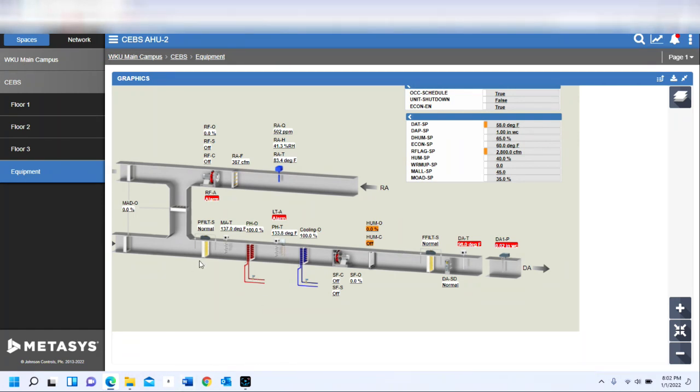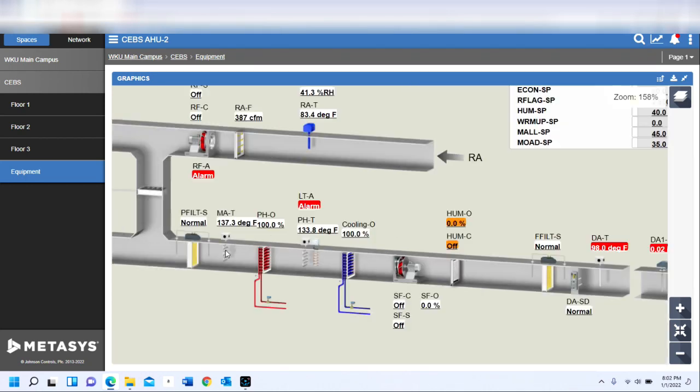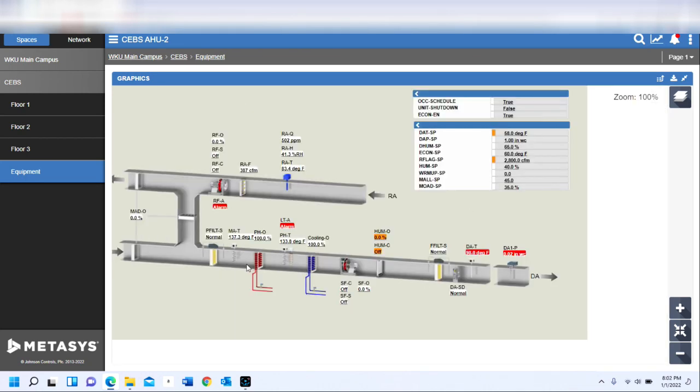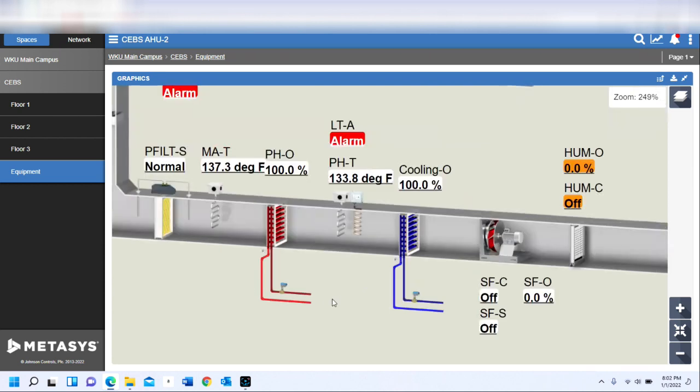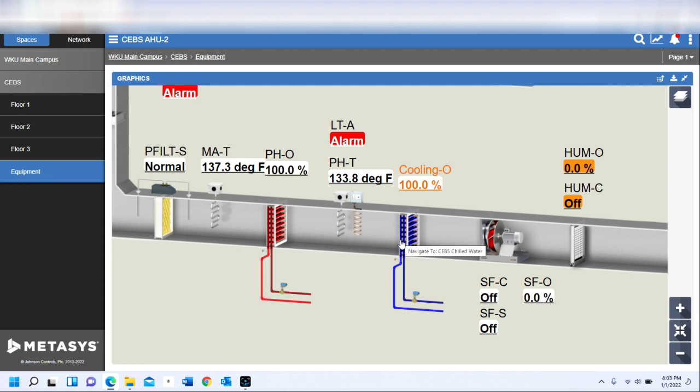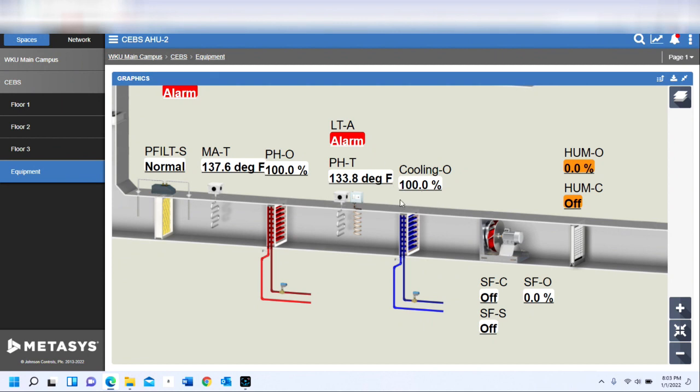One of the things that you can do when you're setting up some of the links within the graphics of your devices: many of the components you can actually link to other systems. For example, here we have our preheat coil as well as our cooling output coil. If we had an air handler that was discharging high and we noticed that the cooling valve was at 100 percent...